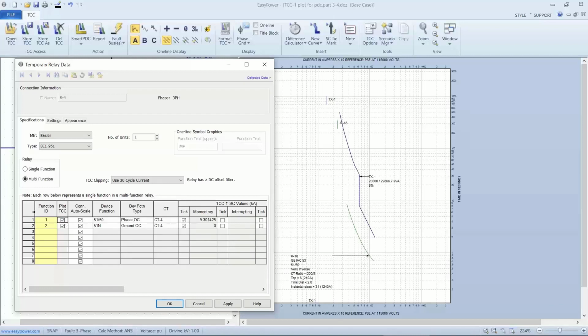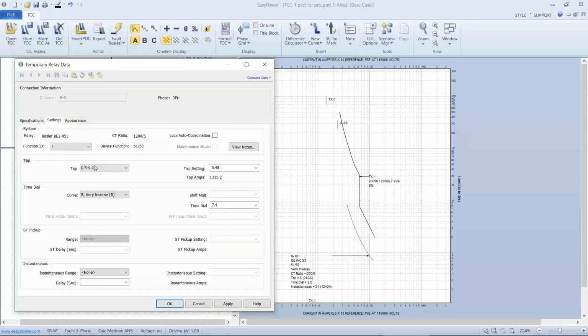Now, the TCC recommendation for full load current on the secondary side is 1250. So let's look at where we have this set. So pickup is at 1315. According to the NEC chart, we could go as high as 3140, 3124. So let's plot it and see how that looks.